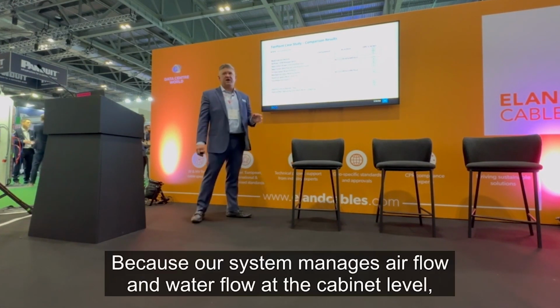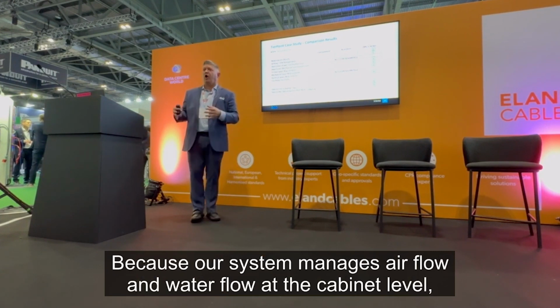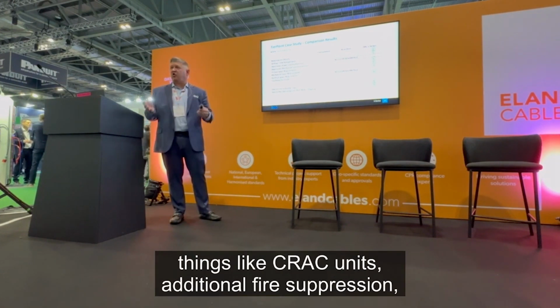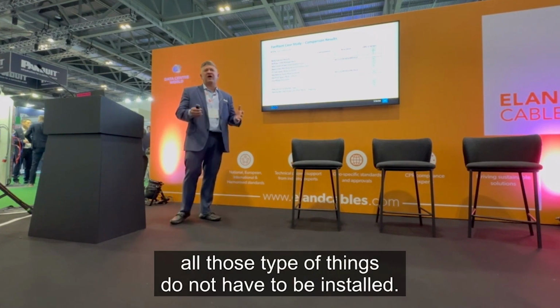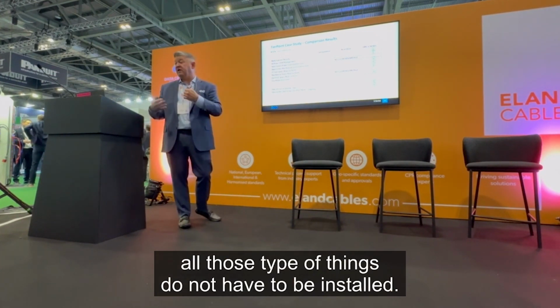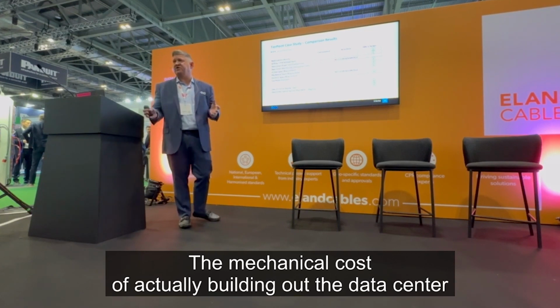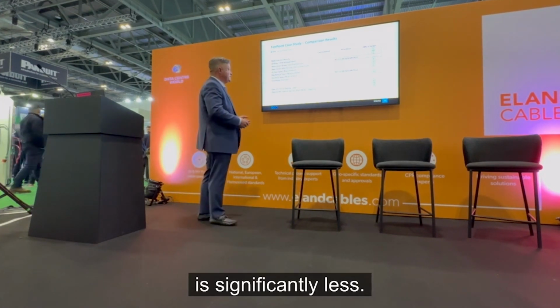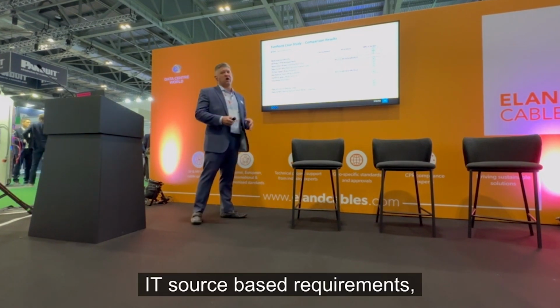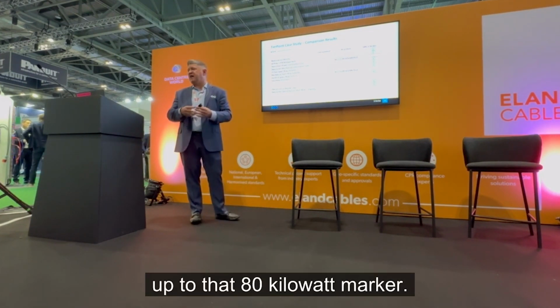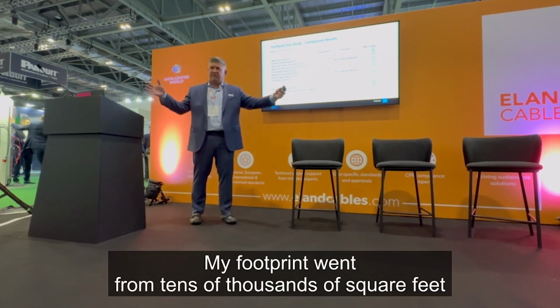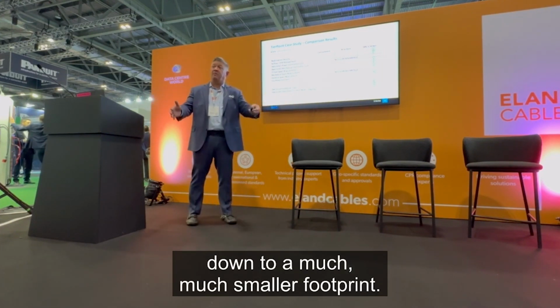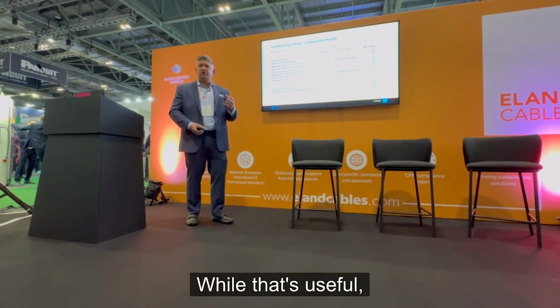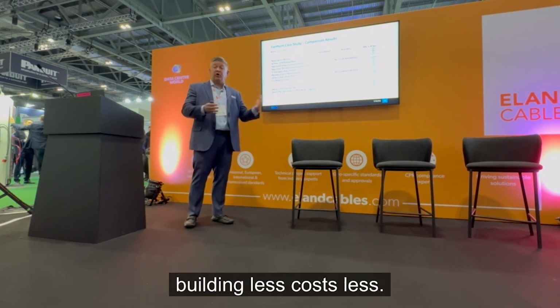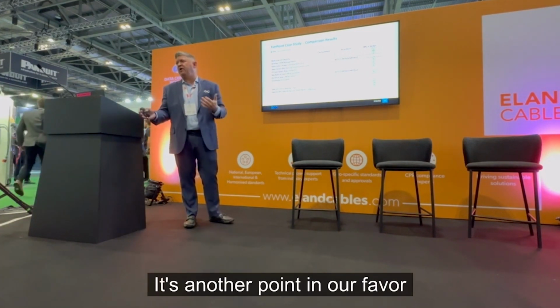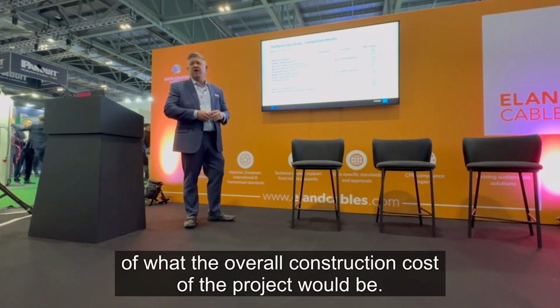Mechanical costs: because our system manages airflow and water flow at the cabinet level, things like CRAC units and additional fire suppression don't have to be installed, so the mechanical cost of building out the data center is significantly less. IT floor space requirements: because we could support the customer at that 80 kilowatt marker, the footprint went from tens of thousands of square feet down to a much smaller footprint. Building less costs less, so that was another point in our favor for the overall construction cost of the project.